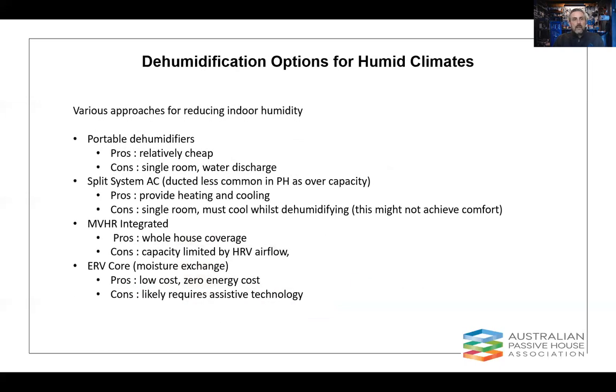If we look at dehumidification options now in humid climates, we've got quite a few different concepts there, and I'll step through some of those. So portable dehumidifiers, they're obviously relatively cheap and readily available. The downside is they are single room, and if they're portable, they're capturing water. At some point, you've got to stop and discharge that water. Split system ACs. Now, you're probably aware that whenever they're cooling, they're also dehumidifying. So that is an option.